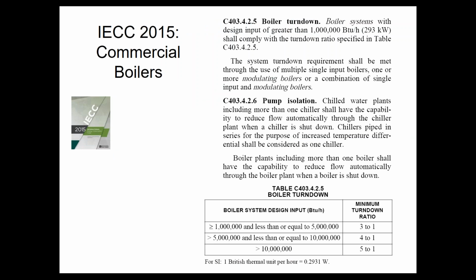For hydronic systems, there are some requirements of noted interest that have changed from last year. The most interesting one is that for boiler plants, if you have more than 1 million BTUs of heating, you have to have a 3-to-1 turn-down ratio. That means you either need 3 boilers, each one of them doing 333,000 BTUs or whatever, or you need 1 boiler that modulates down to 33%, or I guess 2 that modulate down, right? And as you get bigger plants, 5 million or 10 million BTUs, you need either more boilers or more modulation, right? So you can no longer take out an existing 1-stage boiler and put a 1-stage boiler back in.